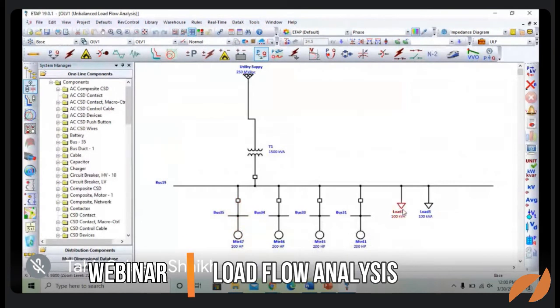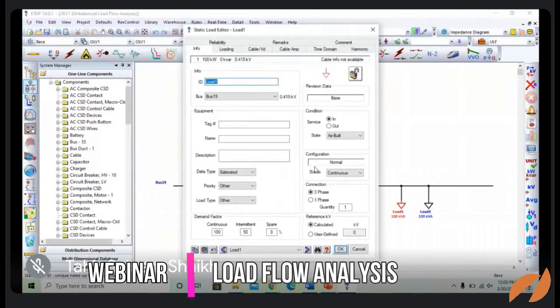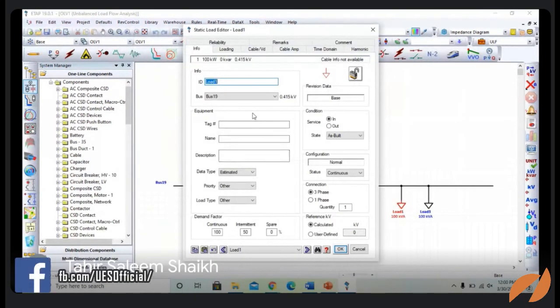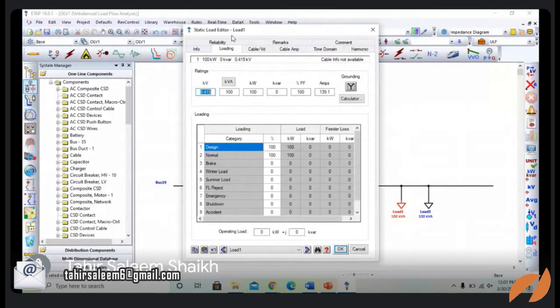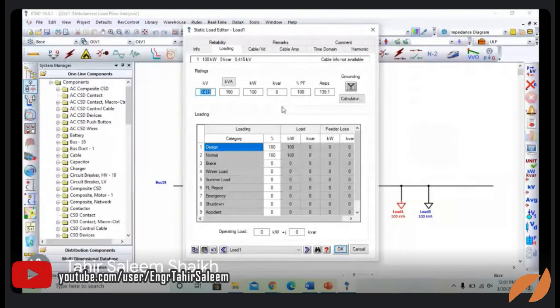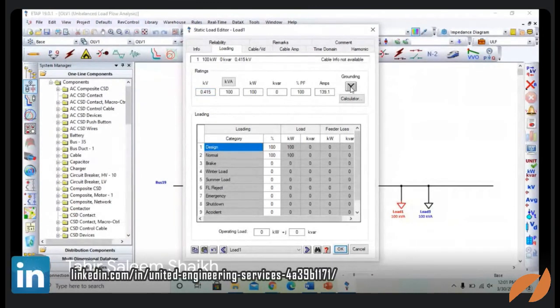These are the static loads. These are just simple loads which have a constant power, sorry, constant kVA load. Here I have selected only the kilowatt load. I have not inserted any reactive load over here, and we have a star grounded load. This is a star grounded load.